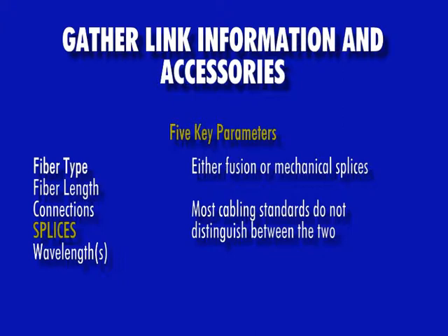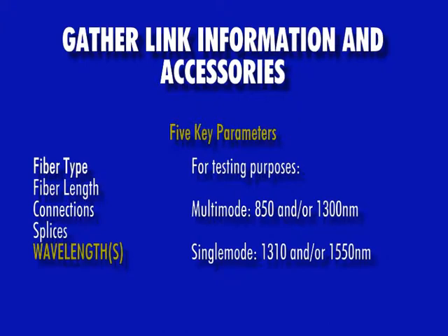For the purpose of calculating a link budget, most cabling standards do not distinguish between fusion and mechanical splices. Lastly, the user must determine what wavelengths they will test at. For multimode, this is 850 and/or 1300 nanometers, and for single mode, this is 1310 and/or 1550 nanometers.